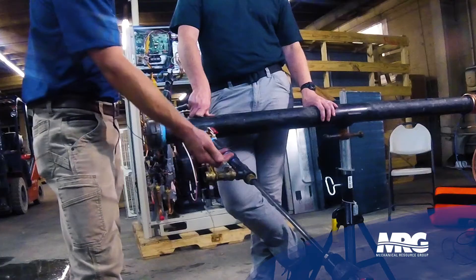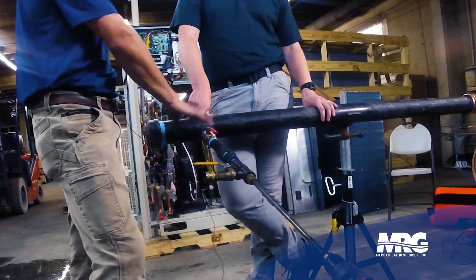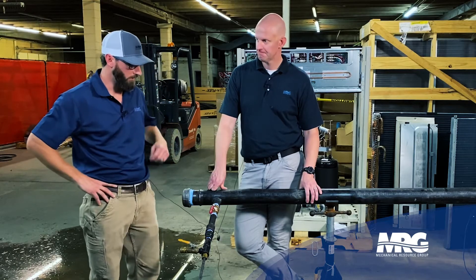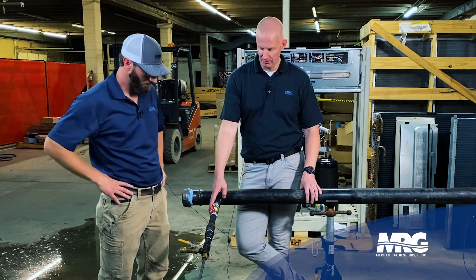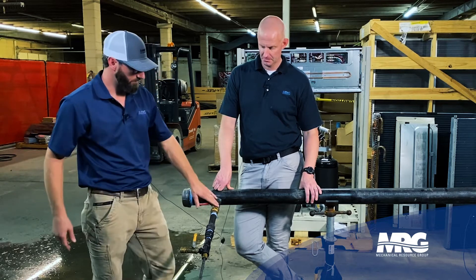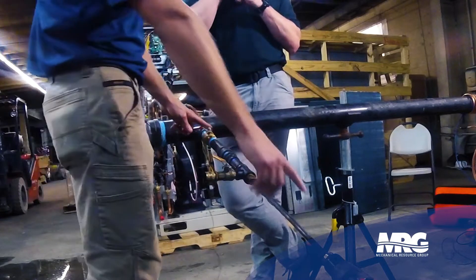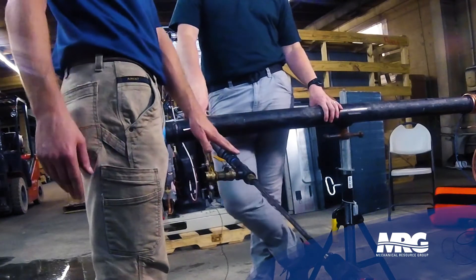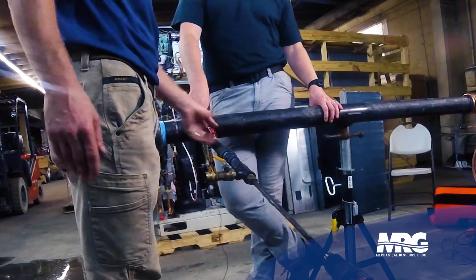At that point, we've got this hot tap setup that has a valve here that you can use to drain your pressure once you're tapped into the line. You could run a hose off that and run it outside if needed, so you don't create a mess. This valve here will be the isolation valve that stays in the system. We've got a shaft that has, in this particular one, a half-inch hole saw bit.